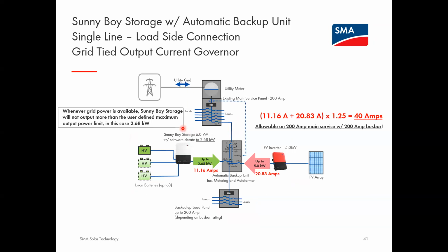So when the inverter is operating in grid-tied mode, it's only capable of outputting up to 2.68 kilowatts at any given instant. And in doing so, I'm able to stay within the limits of my 120% rule. In this case, I have a 200 amp main breaker on a 200 amp bus bar, and therefore I'm allowed a maximum of 40 amps. So I'm able to stay within the limits of the 120% rule by doing this.